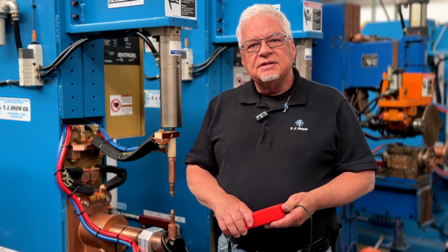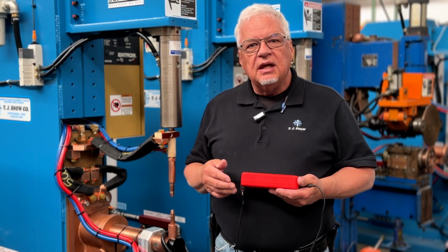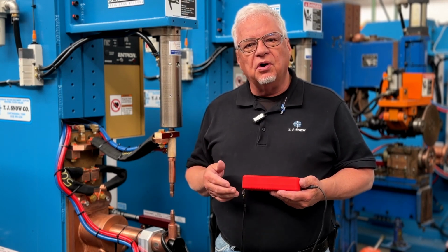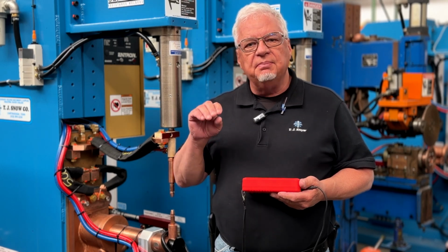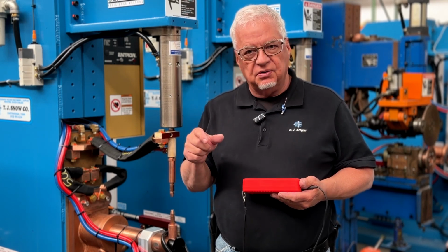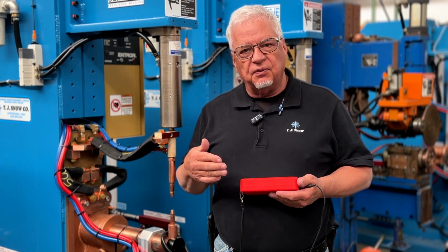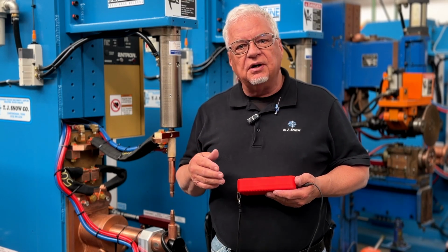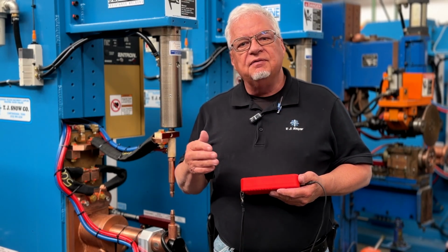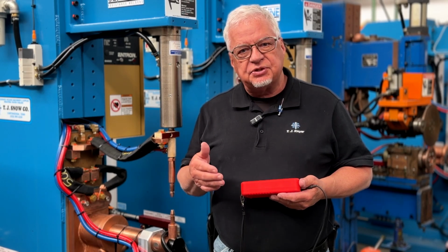It really depends a lot on how you have set up that schedule. If your weld control has a thing called constant current, you are submitting a value of the current that you're asking for. Or you have a percent current. A percent current is a percentage of the amount of energy out of the transformer or that given tap switch.